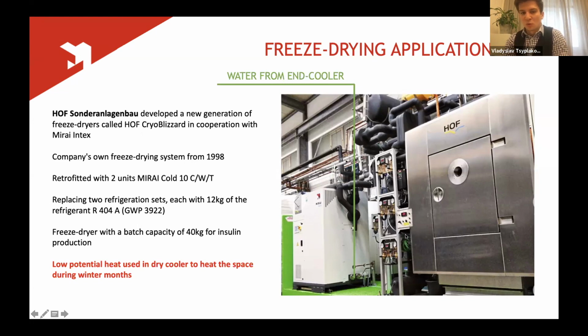So this is the company's own freeze dryer from 1998, but they retrofitted it with two Mirai Cold CWT units. This replaces two refrigeration sets, each with 12 kilograms of R404A. With GWP of almost 4,000, you can do the math, how much more benefit that does to the environment. And this allows to freeze dry batches of up to 40 kilograms for insulin production. So in the next slide, I can show you how, here is the point for the water circuit.